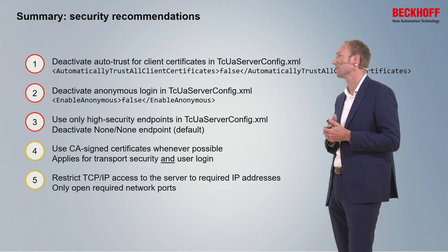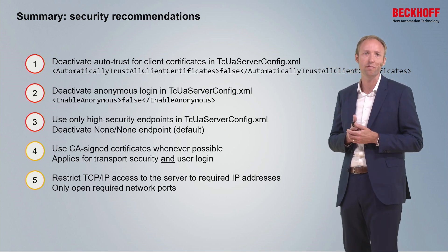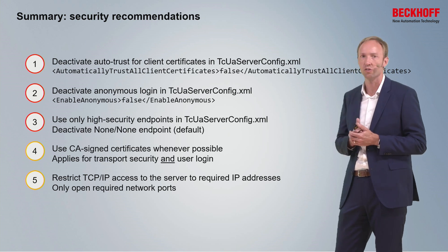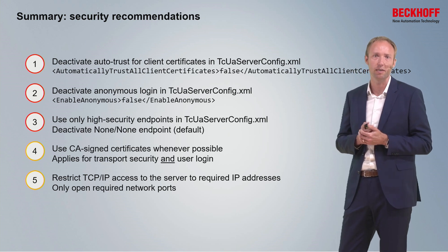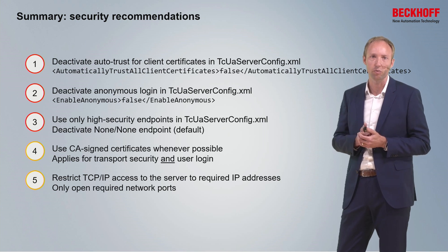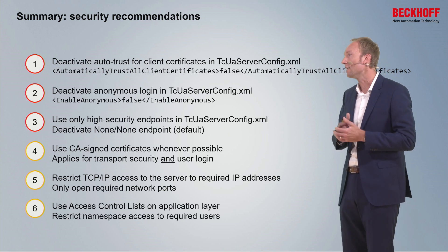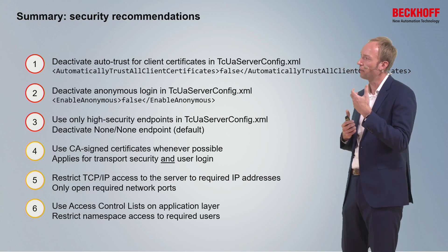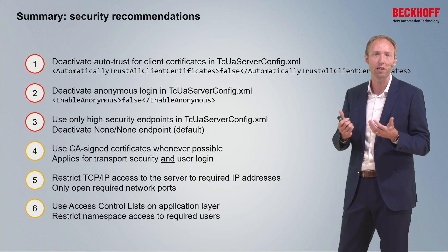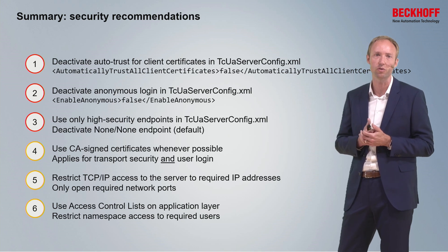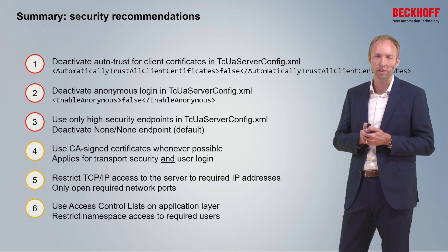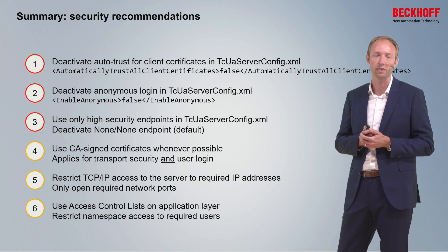Fifth, restrict TCP/IP access only to required IP addresses — for example, only the IP address of your OPC UA client. The Windows operating system and TwinCAT BSD give you plenty of options to configure the corresponding firewall. Finally, give access control lists careful consideration — it is possible to restrict access on namespace level or node level to certain users or user groups, as shown in the TwinCAT OPC UA configurator, giving you fine-grained control over what information is shared on your TwinCAT OPC UA server.